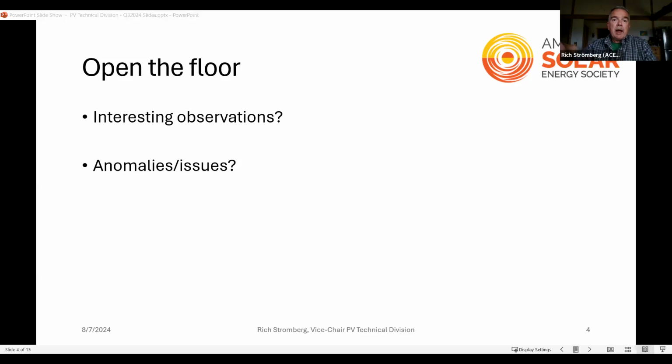it's possible to have hail come in of a certain size that does not crack the front tempered glass, but it still transfers energy through the glass into the much thinner silicon cell underneath, and can cause microcracking. Then over the weeks and months of daily and seasonal thermal cycles, those cracks will expand and propagate and eventually start isolating parts of the cell. So you may do some electrical testing right after the hailstorm and it's looking pretty good. You check it 4 months later, you might see noticeable losses.